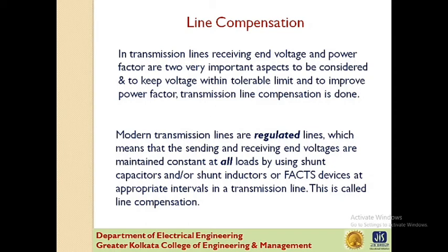Generally, compensation consists of injecting reactive power to improve power system operation. More specifically, to keep voltage close to nominal values, reduce line currents and hence network losses, and contribute to stability enhancement. Most often, compensation is provided by capacitors, counterbalancing the predominantly inductive nature of either the transmission system or the loads. Most of the loads in a power system are inductive. It also may consist of reactors where reactive power absorption is of concern.